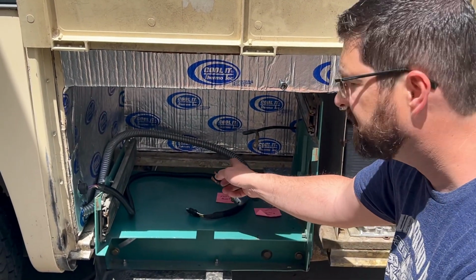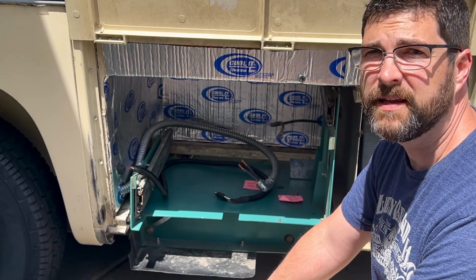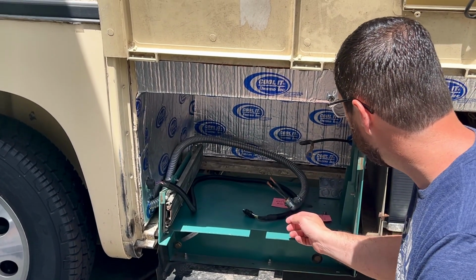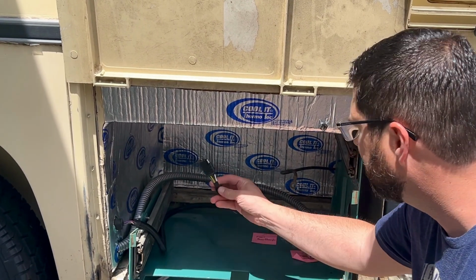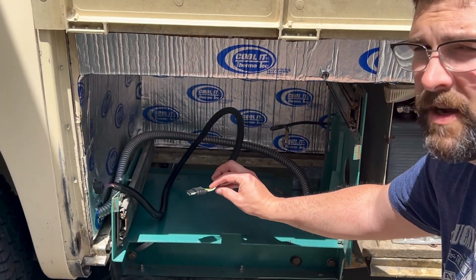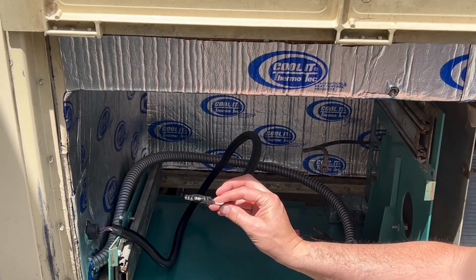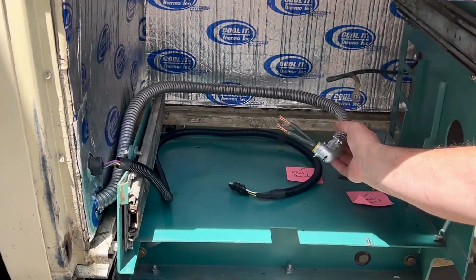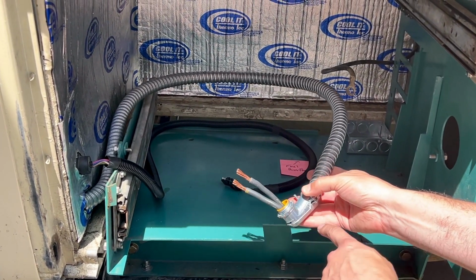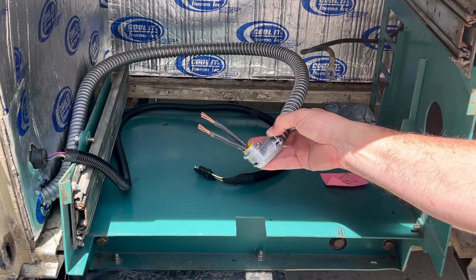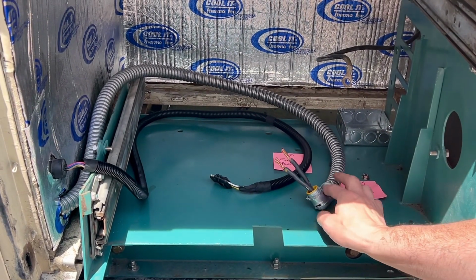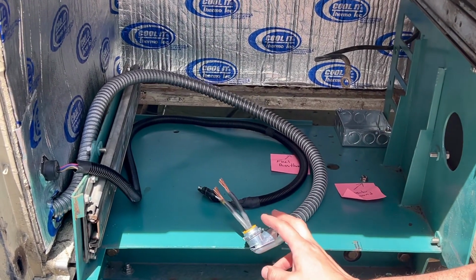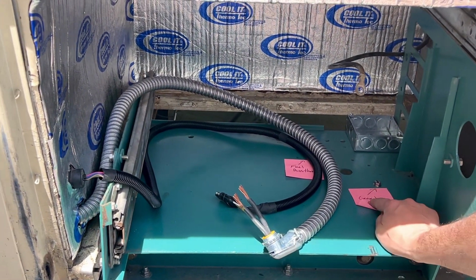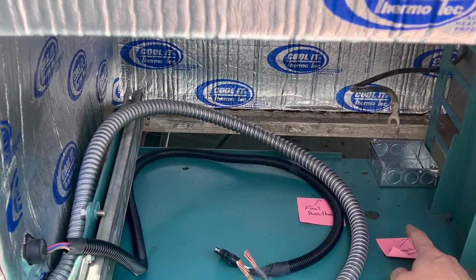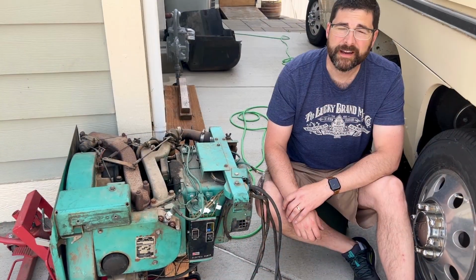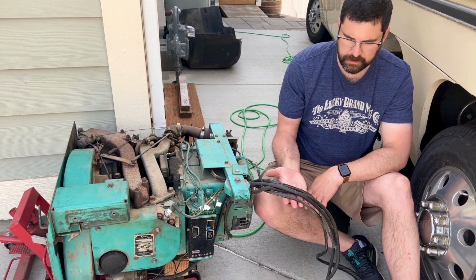So I think I'm going to skip the complexity of running it underneath the case and insulating all that. I've also found that getting this wired in is going to work pretty well—I've wired that mating connector to the back of the generator. I've got my conduit set up here to run into the box, and then I'll connect this to the output on the generator. I am going to ground the generator right here; this is a threaded hole that the ground wire coming off the back of the generator will ground to. All right, let's talk a little bit about what we've got going on the back of the generator here.